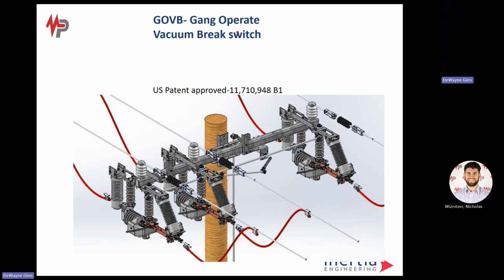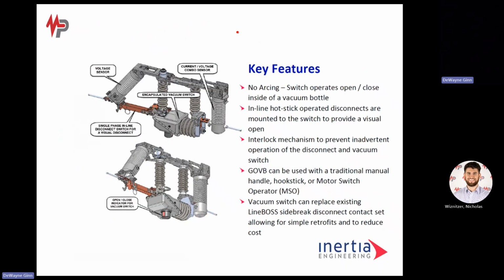This switch is, let me go to the next slide. And there we go, current and voltage. These would be single phase units. How does this work? There's no arcing and sparking in this particular switch. All the switches we manufacture are side break or air break switches. Now this is a vacuum switch, so it's got a vacuum bottle internally.